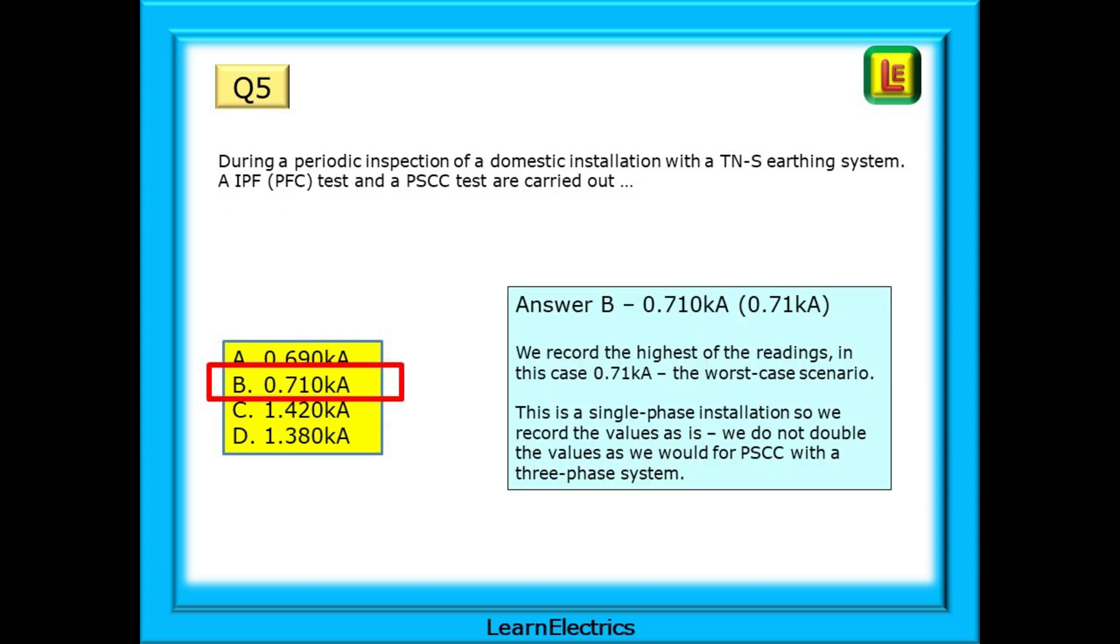The answer is B, 0.710 kiloamps, shown as 0.71 kiloamps on some test meters. We record the highest of the readings, in this case 0.71 kiloamps, the worst case scenario.